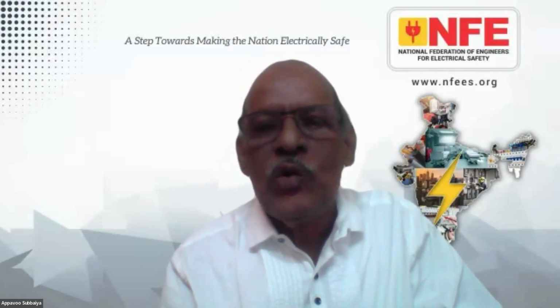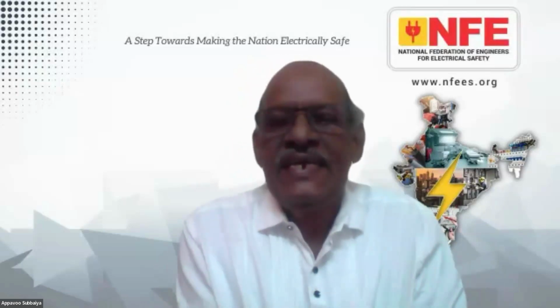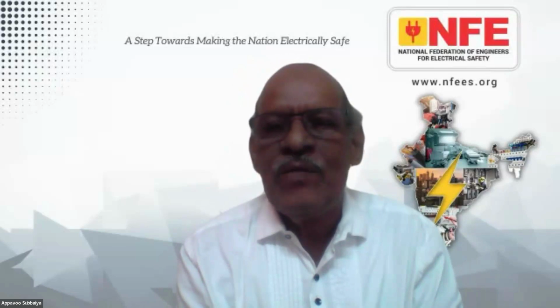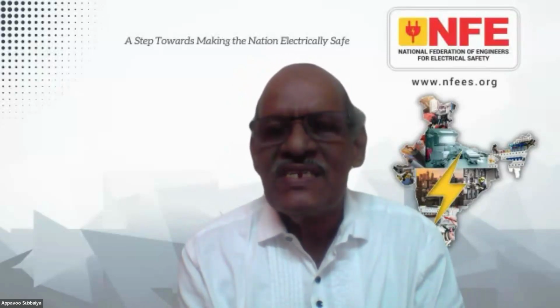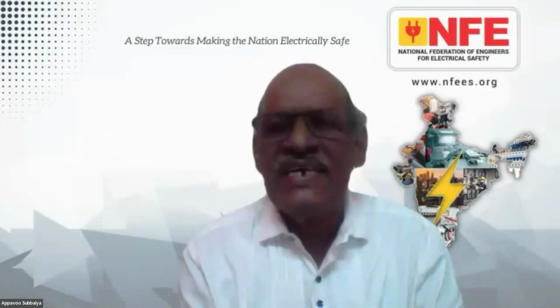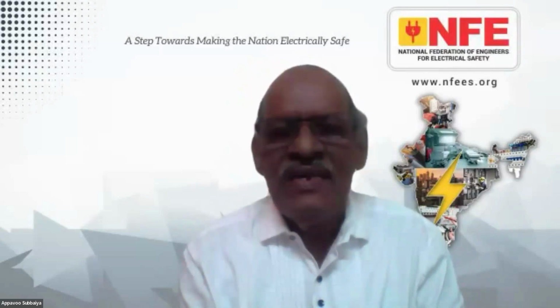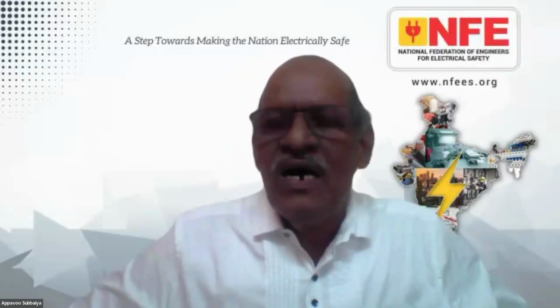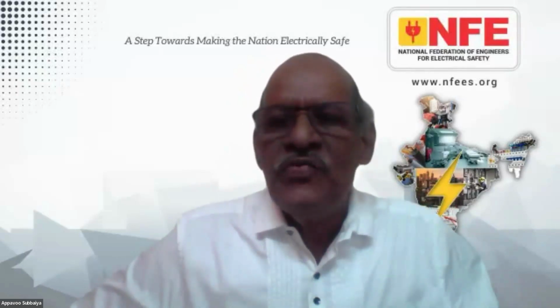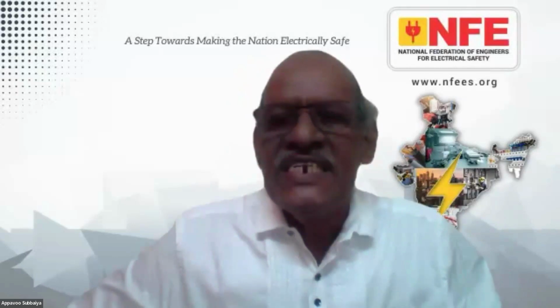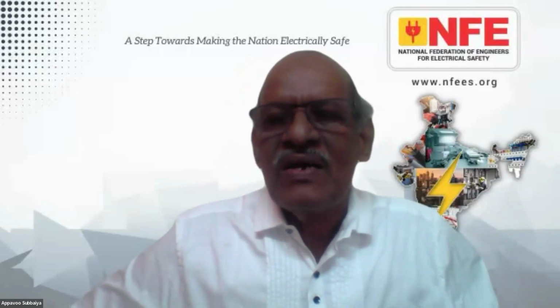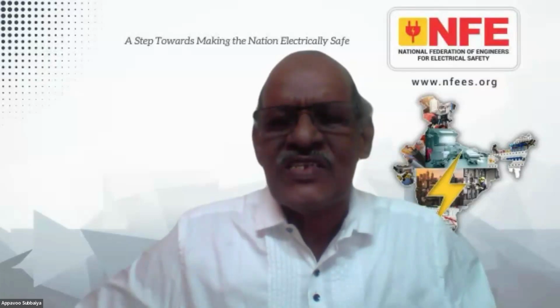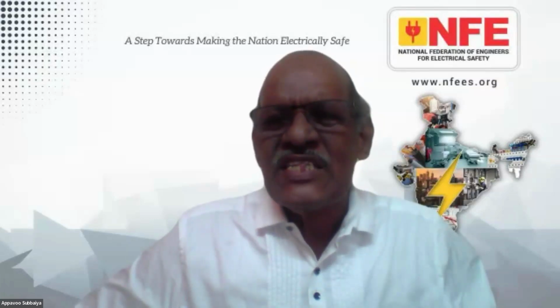in an underground earth grid continuity. That is totally missing in our country. And the major contributor is the consumer. Have we ever provided earth? Do we know that there is an earth electrode in our premises? We enjoy a luxurious house at a cost of 1 crore. We fail to provide an RCD worth 3,000 rupees or an earth rod that is sufficient at a cost of less than 1,000 rupees.